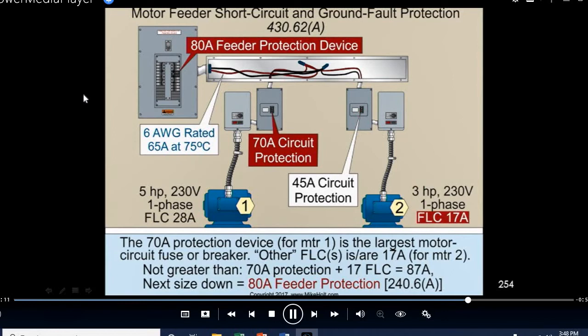Right? Right. Now, watch the logic here. If this motor starts first, that means you've got 17 amps going. Is that right? Yep. Then this motor starts. That means you have 17 plus 70. You have 87. You follow the logic? Not bigger than 87, so 80. But what about if this motor started first? This motor has 28, right? Then you'd have 28 plus what? 45. That gives me 73, not bigger than 70. Now, if both motors start at the same time, okay, well, now we might have a problem because now you're going to have 70 plus 45. So the assumption is that the motors are all running except the largest one. Then the largest one starts. That's the logic there.